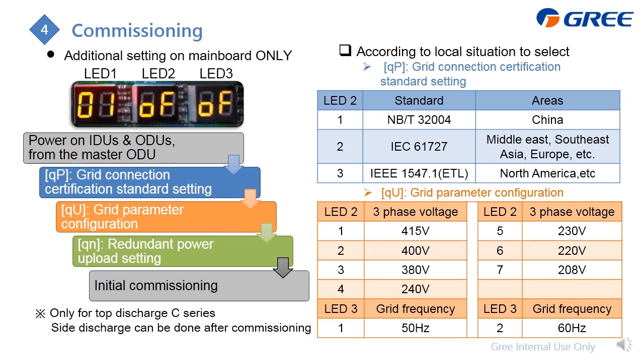After that, it's just the regular commissioning stage as with the regular GMV. The commissioning methods are the same. You can do it on these three: from the outdoor unit PCB, from the debugging software on your PC, and from the portable debugger. But the setting of these three parameters can only be done on the outdoor unit PCB. As for the side discharge, it can be done just after the commissioning, and before the commissioning, especially for the C series, you need to do this one.